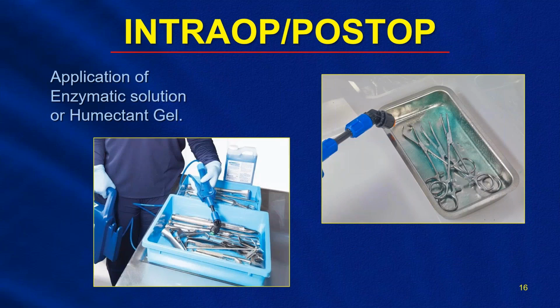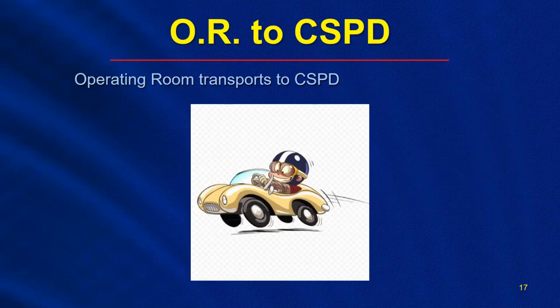This method of wiping down instruments and applying an enzymatic solution to them is known as point-of-use cleaning. Now, the enzymes in the humectant gel begin the breakdown process of the bioburden left on surgical instruments from the procedure. This is extremely important because if bioburden is left to dry on instruments, it may lead to the formation of biofilm. So after that, the OR will send the soiled instruments back down to central sterile for reprocessing.